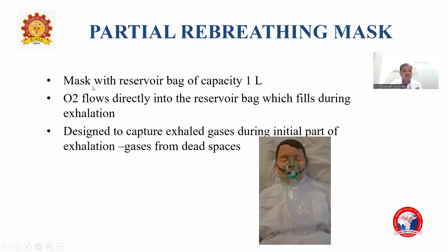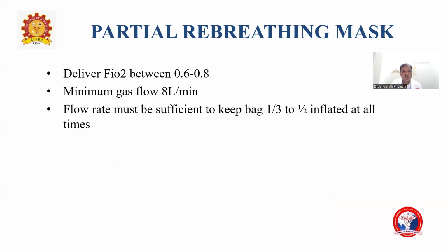Partial rebreathing mask. It is a mask with a reservoir bag of capacity 1 liter. Oxygen flows directly into the reservoir bag, which fills during the exhalation. It is designed to capture exhaled gases during the initial part of the exhalation. These initial exhalation gases are captured in the bag and used for providing inspiration because they do not contain carbon dioxide, as they are coming from the anatomical dead space, which has not taken part in the gas exchange.